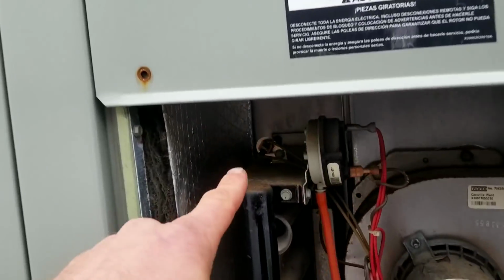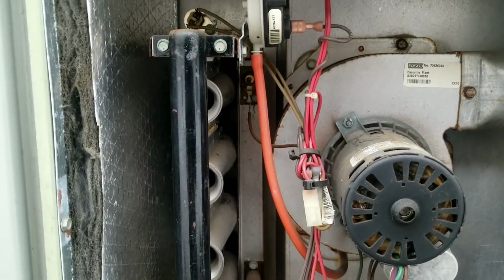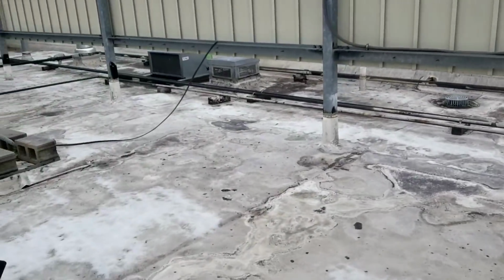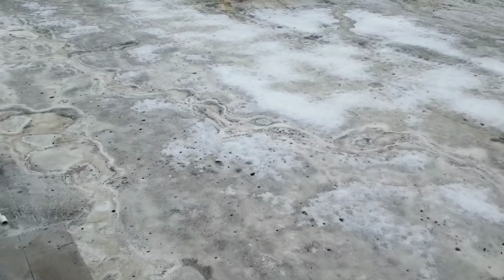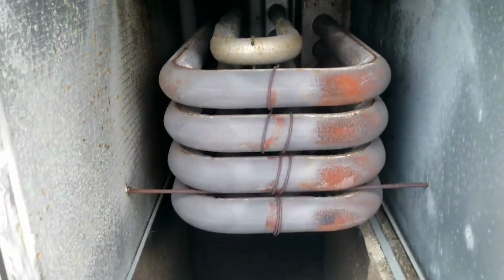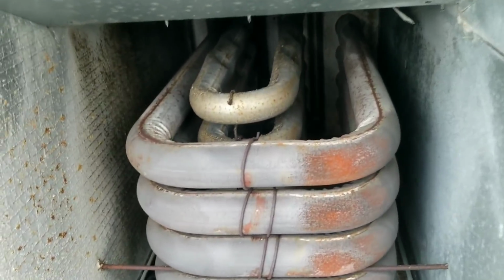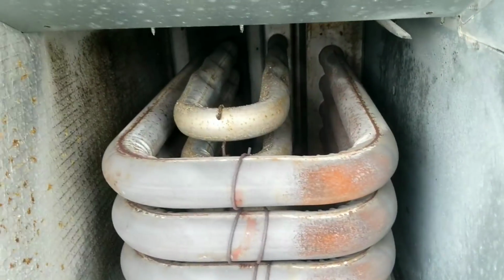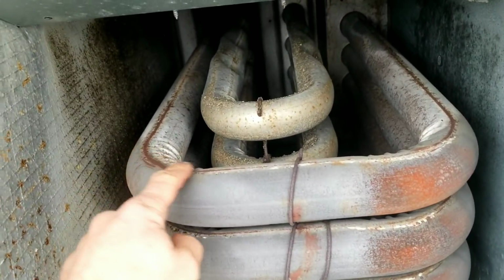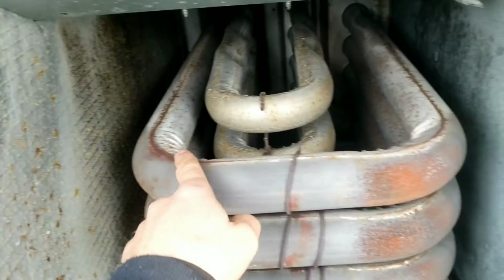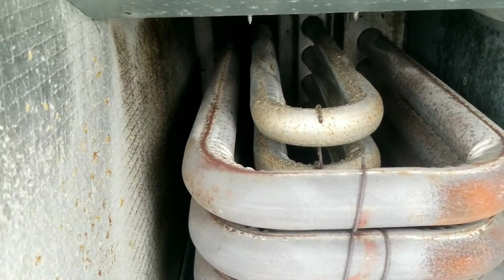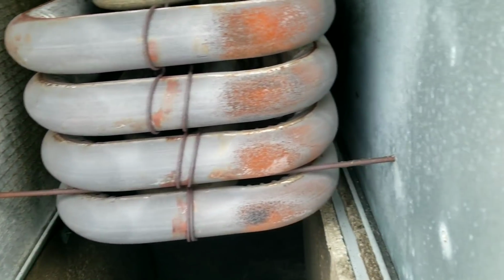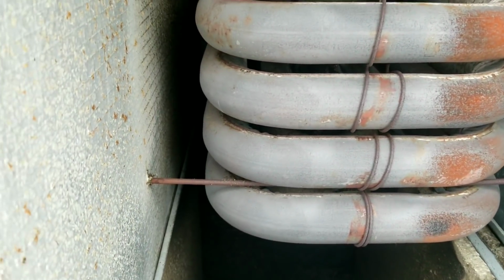Alright, so before I just go ahead willy-nilly and resetting our flame rollout, that little guy up there, let's double check our heat exchanger, because you never know. This unit's not that old, but you just never know. Alright guys, here's our heat exchanger. Now, I know it looks fairly bad, and it is, but the majority of this I've scraped all along these seams with a screwdriver. I don't have any soft spots. I don't have any openings. There's no visible cracks. Like I said, there's no weak spots.